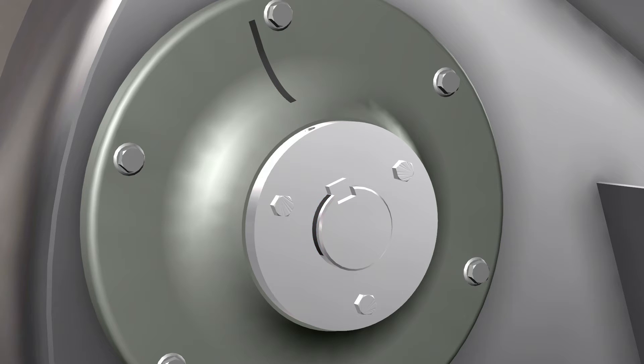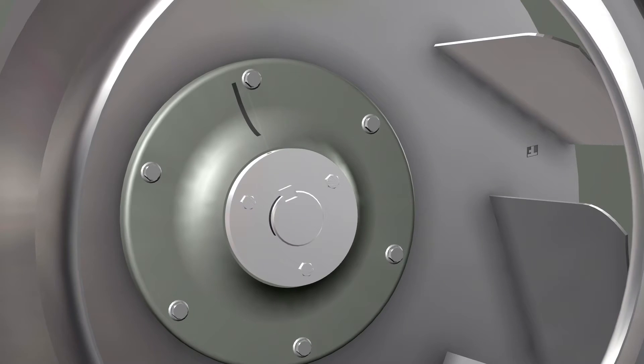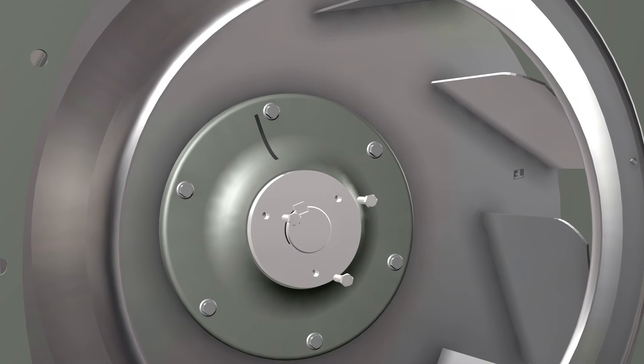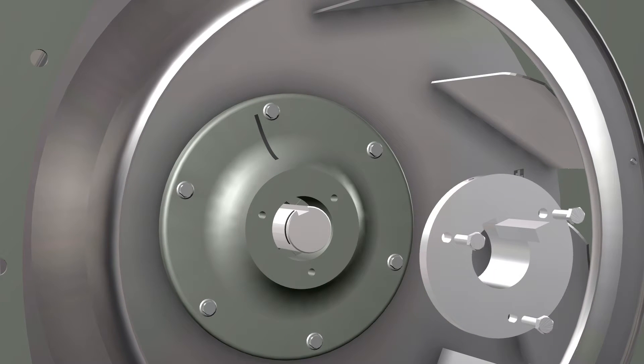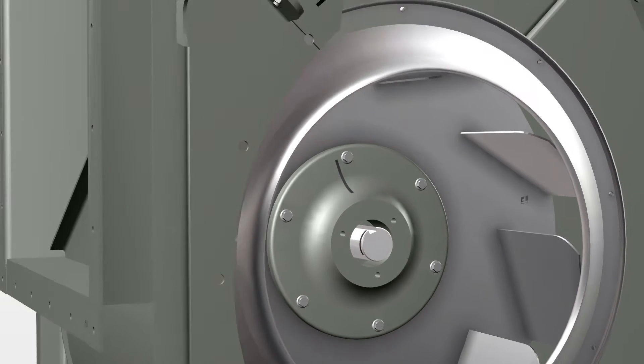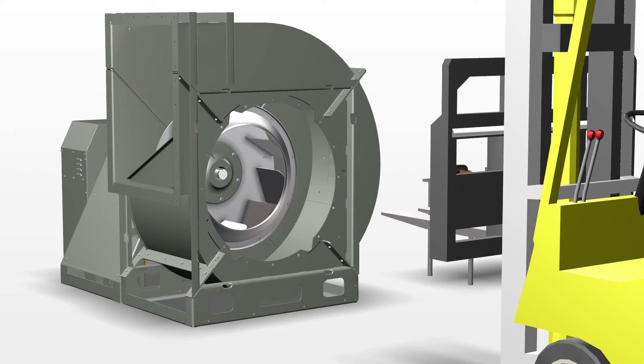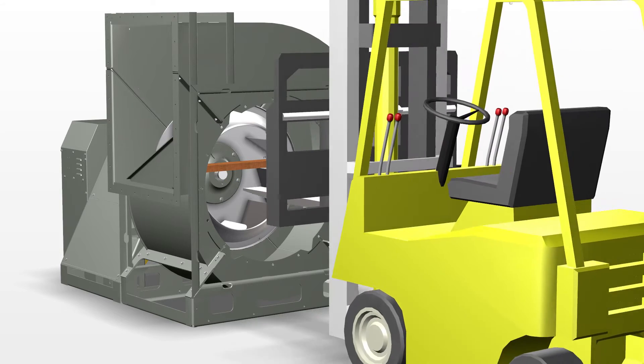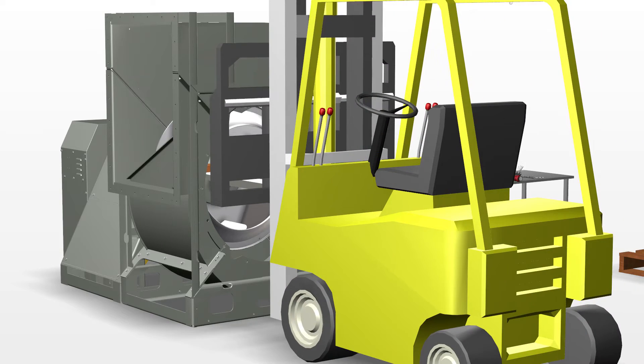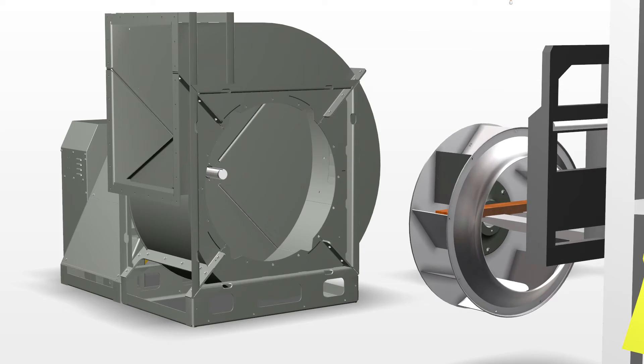Loosen the set screw in the bushing. Remove the bushing according to the instructions found in the fan pack. Once the bushing is removed, remove the wheel with the forklift. It helps to put a block of wood across the forks to help balance the wheel. Smaller wheels can be lifted out by hand.